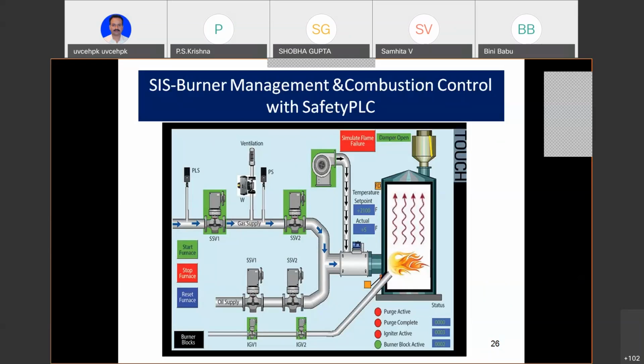An analog input card for a normal PLC would cost something like 10,000, and don't take the figure too seriously. But the analog input card for the safety PLC would cost almost 6 or 8 times that. That is the beauty of those PLCs: reliability, higher SIL factor. I told you SIL is an example of safety performance. We'll talk briefly on SIL.